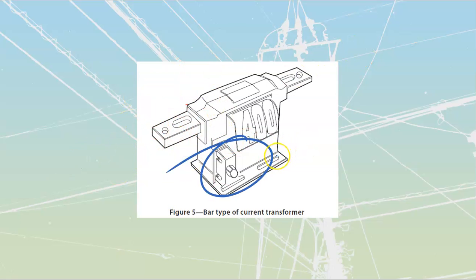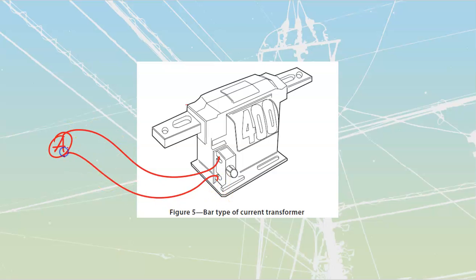This is a clear little window. Inside here is where I'll have the 5 amp terminals, so my actual meter connects through to the ammeter. When I remove this case, there's a little spring-loaded bar inside that should bridge across those 2 terminals. I can remove this, access the screws, and pull these wires out from underneath. It should always be a clear cover so you can see what's going on inside.